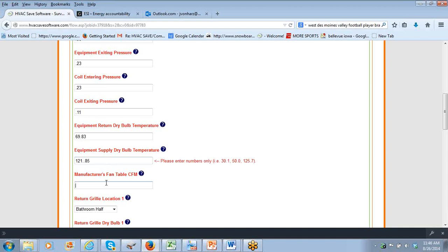If you round up on the high end and round down on the low end, if you, let's get her down to 1/10 of a degree. I don't know why that entry validation was looking for something different. I'll have to look at that, but we'll get it there. But my point being is if you round up on the high end and round down on the low end, it could be 2%. It may be the difference between a pass or a fail. So make sure you get it down to 1/10 of a degree.